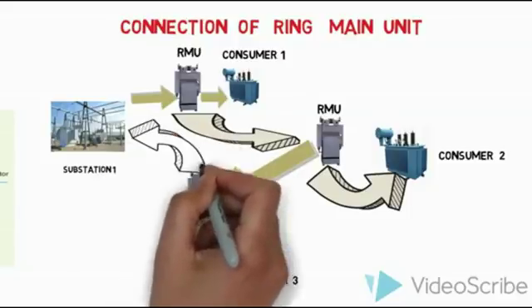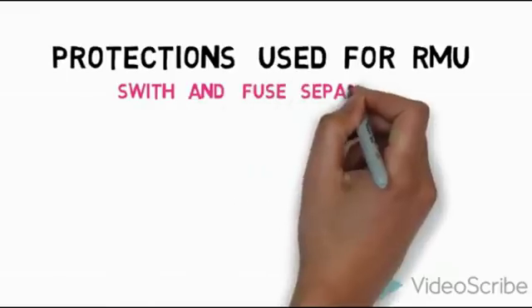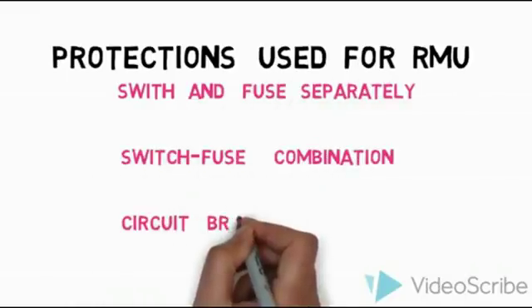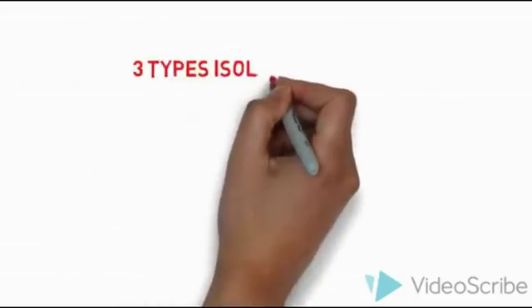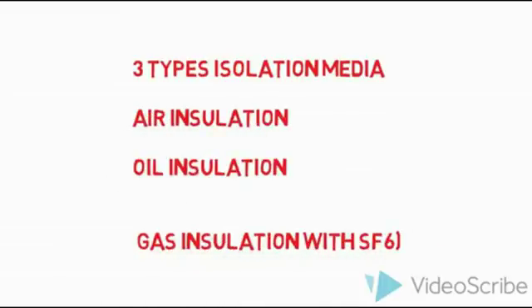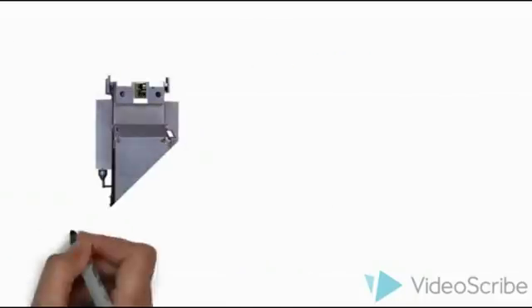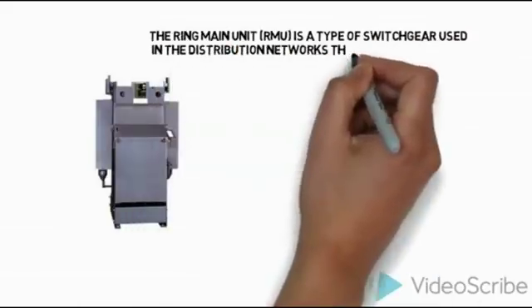This is a very easy way to rectify faults — for cable maintenance or any maintenance. The protection in a ring main unit is mainly of three types: switch and fuse separately, switch-fuse combination, and circuit breaker. For insulation, three types are used: air, oil, and gas — specifically SF6 gas. These three media are used for insulation purposes.